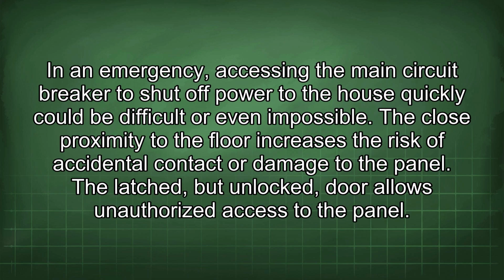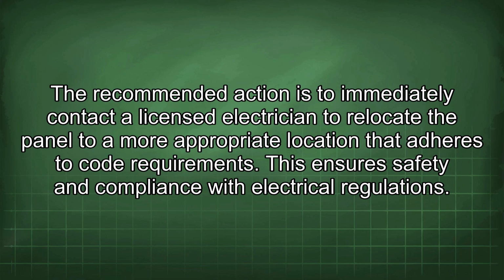In an emergency, accessing the main circuit breaker to shut off power to the house quickly could be difficult or even impossible. The close proximity to the floor increases the risk of accidental contact or damage to the panel. The latched, but unlocked, door allows unauthorized access to the panel. The recommended action is to immediately contact a licensed electrician to relocate the panel to a more appropriate location that adheres to code requirements. This ensures safety and compliance with electrical regulations.